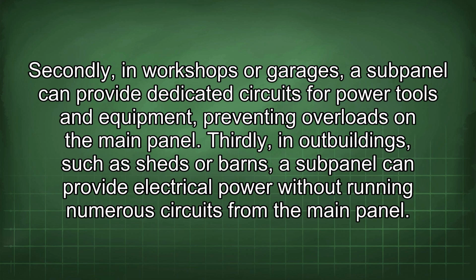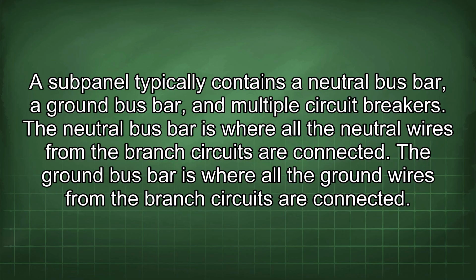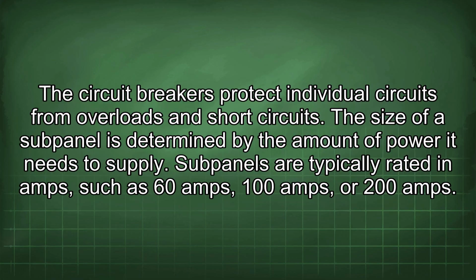A subpanel typically contains a neutral bus bar, a ground bus bar, and multiple circuit breakers. The neutral bus bar is where all the neutral wires from the branch circuits are connected. The ground bus bar is where all the ground wires from the branch circuits are connected. The circuit breakers protect individual circuits from overloads and short circuits.